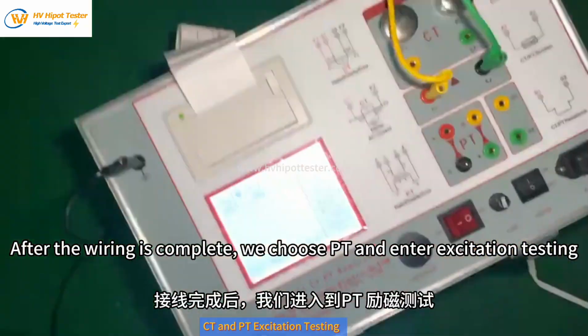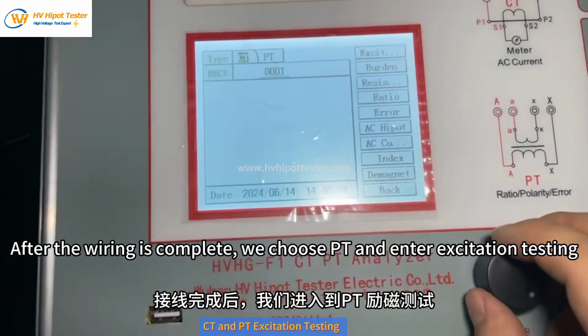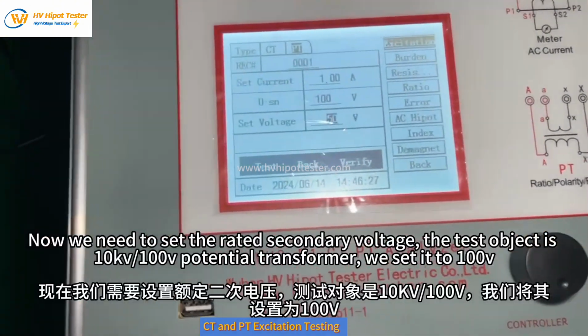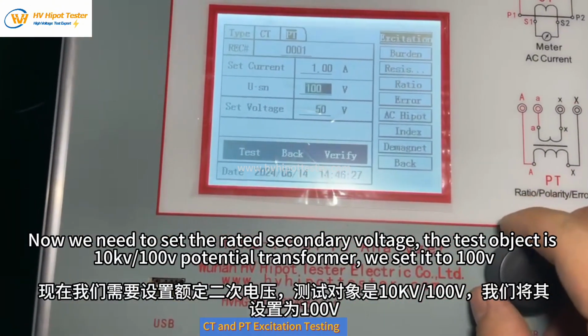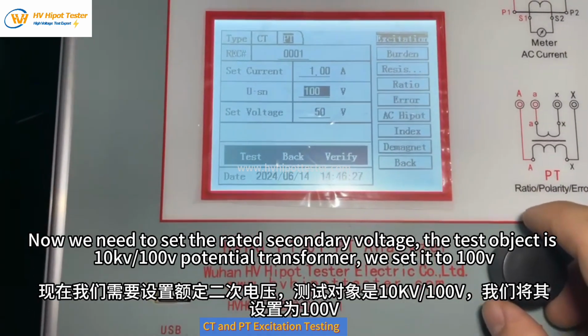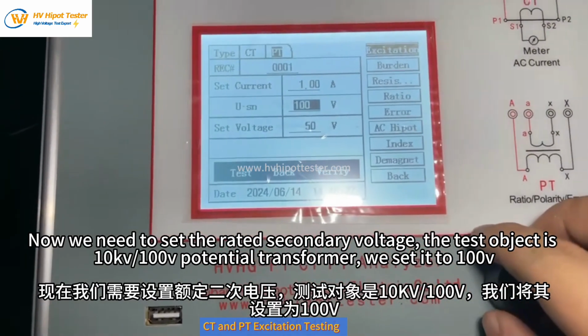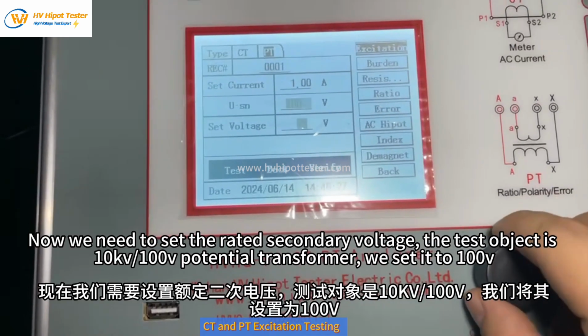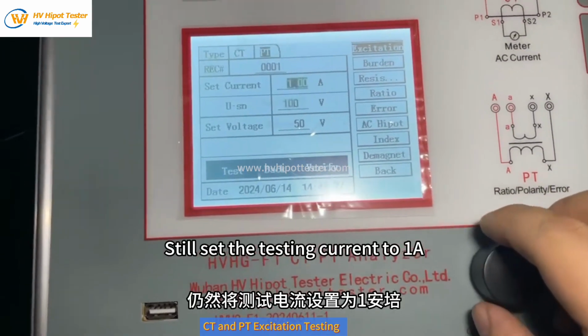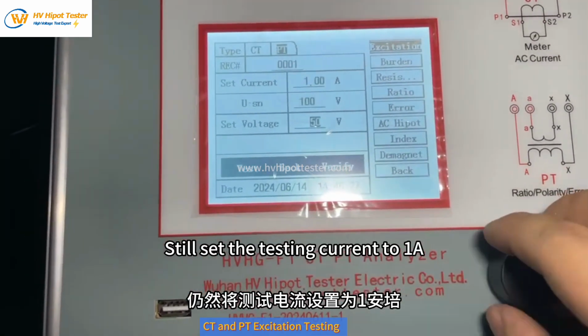After the wiring is complete, we choose PT and enter excitation testing. Now we need to set the rated secondary voltage. The test object is a 10 kV 100 volts potential transformer. We set it to 100 volts. Still set the testing current to 1 ampere.